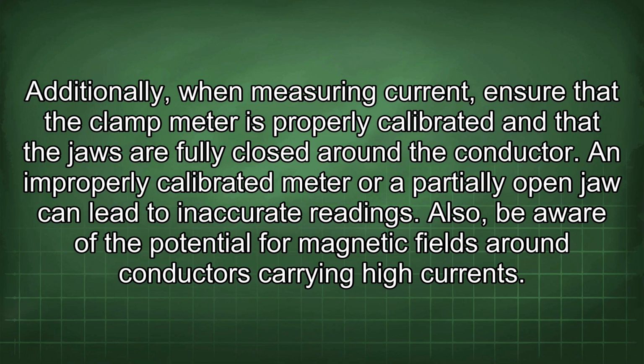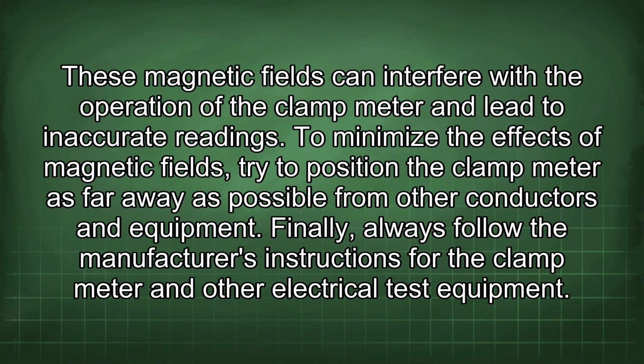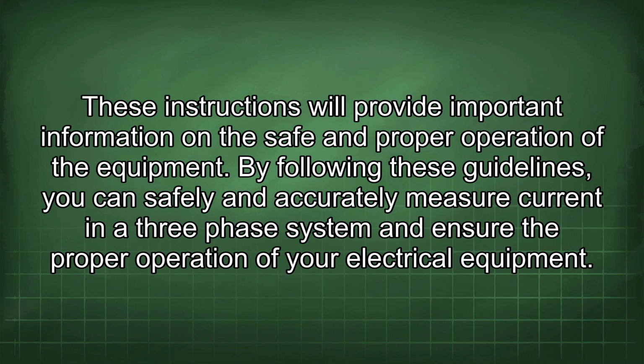Also, be aware of the potential for magnetic fields around conductors carrying high currents. These magnetic fields can interfere with the operation of the clamp meter and lead to inaccurate readings. To minimize the effects of magnetic fields, try to position the clamp meter as far away as possible from other conductors and equipment. Finally, always follow the manufacturer's instructions for the clamp meter and other electrical test equipment. These instructions will provide important information on the safe and proper operation of the equipment. By following these guidelines, you can safely and accurately measure current in a three-phase system and ensure the proper operation of your electrical equipment.